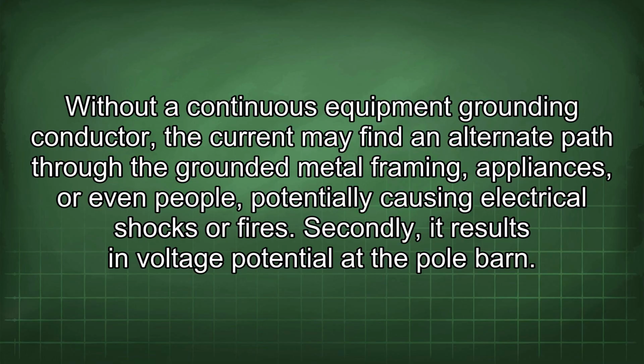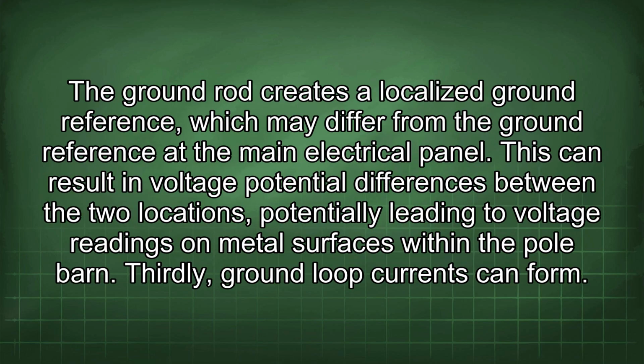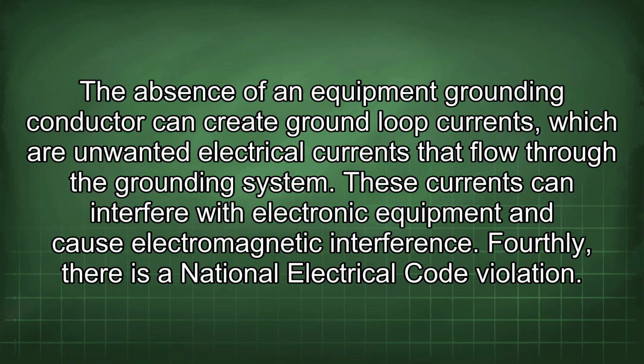Secondly, it results in voltage potential at the pole barn. The ground rod creates a localized ground reference which may differ from the ground reference at the main electrical panel. This can result in voltage potential differences between the two locations, potentially leading to voltage readings on metal surfaces within the pole barn. Thirdly, ground loop currents can form. The absence of an equipment grounding conductor can create ground loop currents, which are unwanted electrical currents that flow through the grounding system. These currents can interfere with electronic equipment and cause electromagnetic interference.